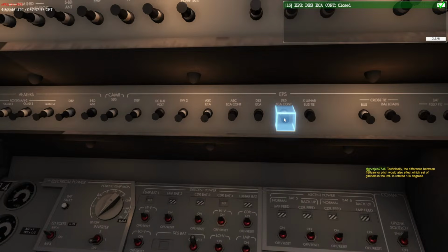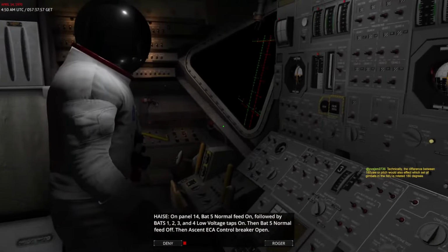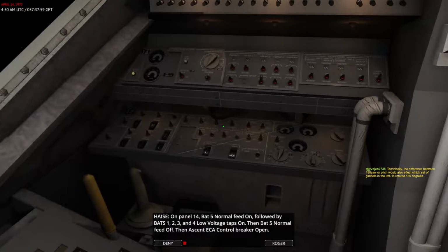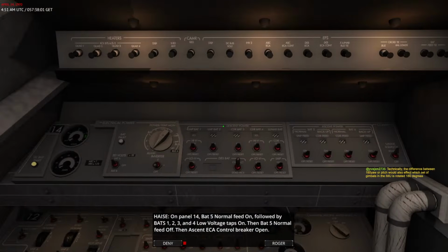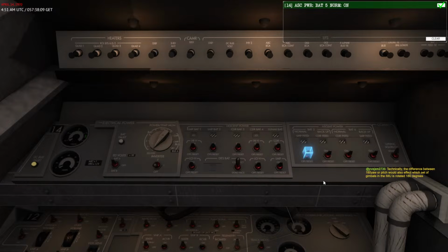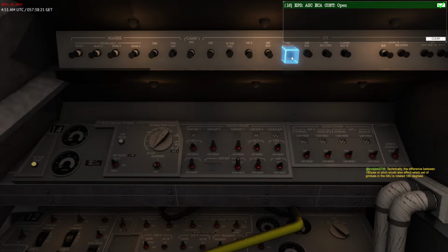On panel 14, BAT 5 normal feed on, followed by BATs 1, 2, 3, and 4 low voltage taps on. Then BAT 5 normal feed off, then Ascent ECA Control breaker open. This one is on, this one is on, this one is on, this one is on. Off, reset, and then opening.